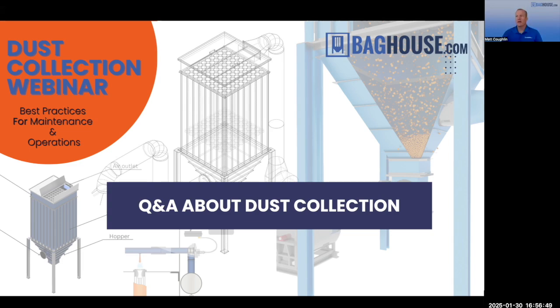Well, so we have a dust collector maintenance checklist, which we've given out to a bunch of different people. Whenever I do these kinds of things, I always like to deliver that checklist as a template because every system's a little different. But the things on that checklist are pretty much the same regardless of your system. It's checking your differential pressure, listening to your pulse valves, doing occasional filter inspections, stuff like that.